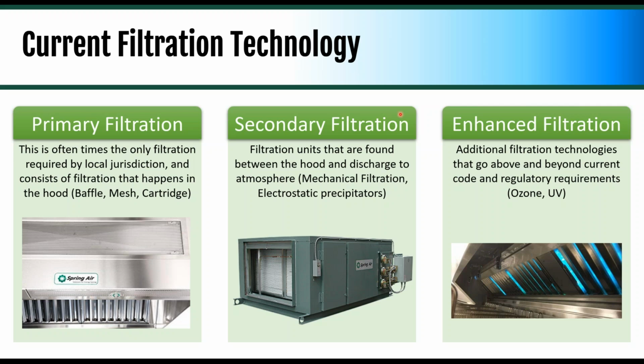with these. The secondary filtration units, which we've been selling for a long time, are found between the hood and the discharge to the atmosphere. There's two main styles. Mechanical filtration, which is what we do, uses a set of media-based filters. Think about your furnace filter, call it on steroids, to remove 99.97% of grease from the exhaust stream prior to being exhausted into the atmosphere. The other thing we don't see in Canada almost at all, but is prevalent down in the US, is electrostatic precipitators. These use a charged plate to basically knock the particles out of the air.